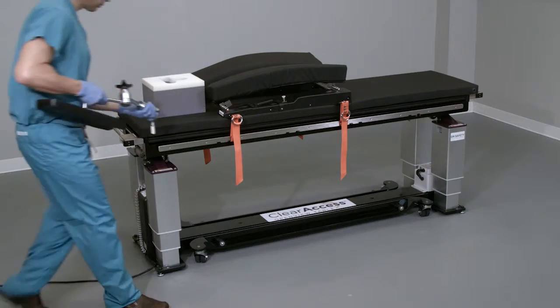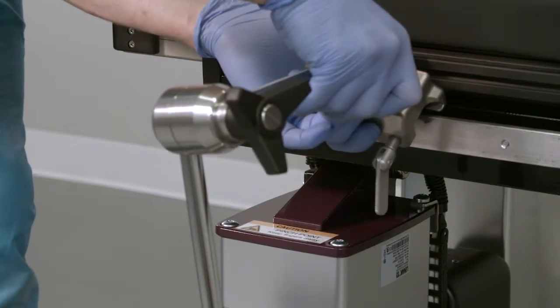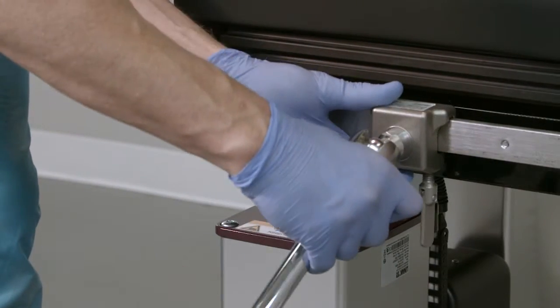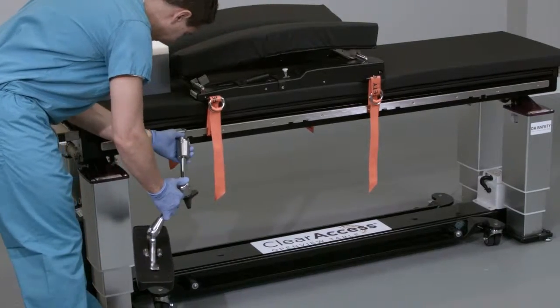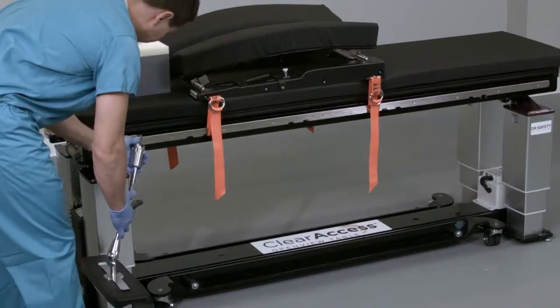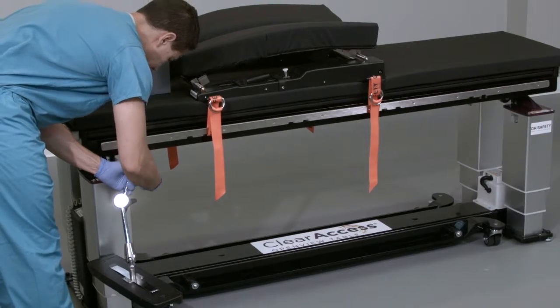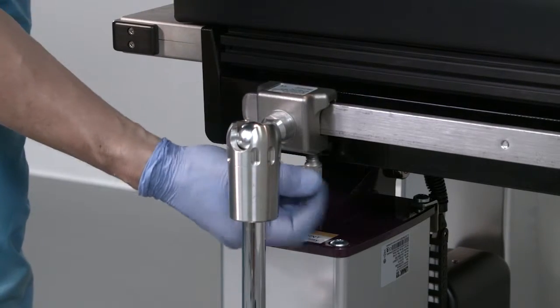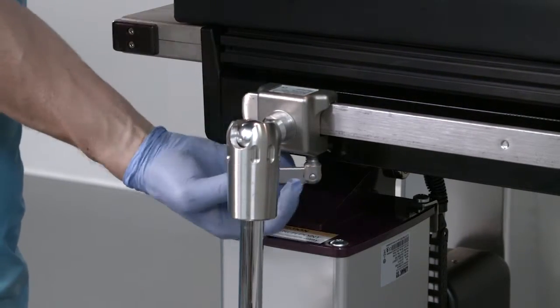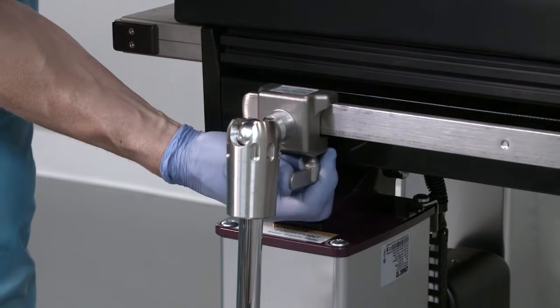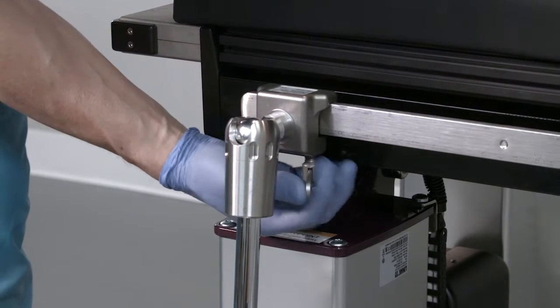to the side rail to engage the top of the side rail first with the armboard lock. Lower the armboard to engage the bottom of the side rail. If necessary, slide the armboard toward the head end or the foot end before locking the armboard onto the side rail. Lock the armboard onto the side rail by firmly hand-tightening the locking mechanism hanging from the bottom of the armboard lock.